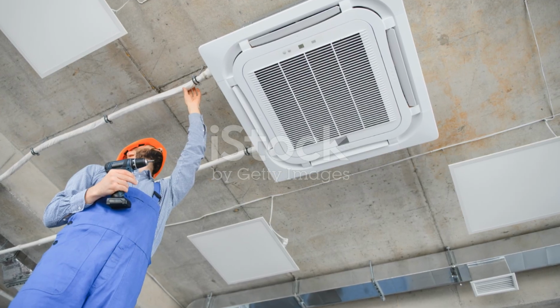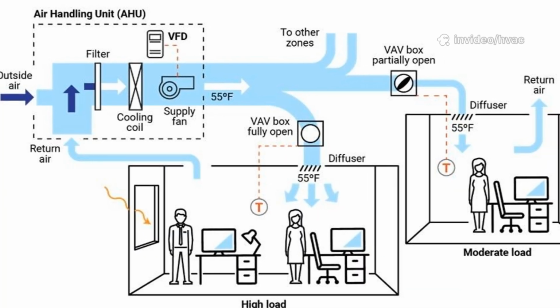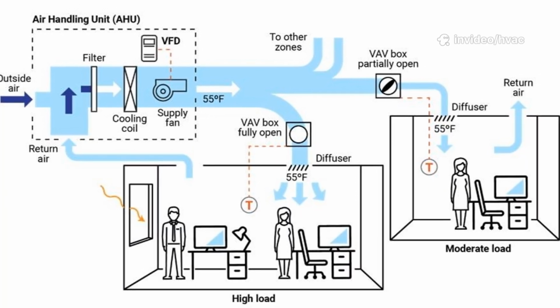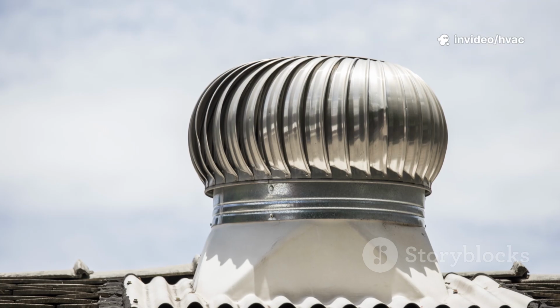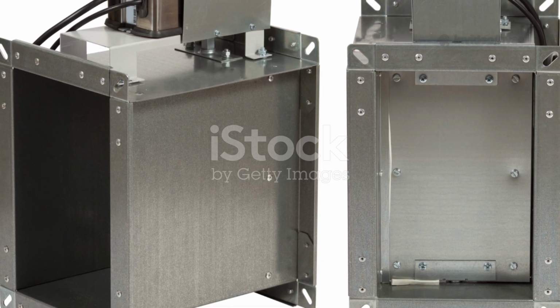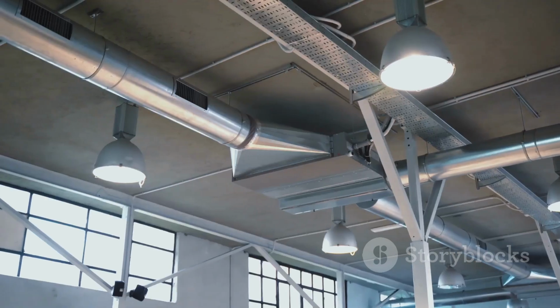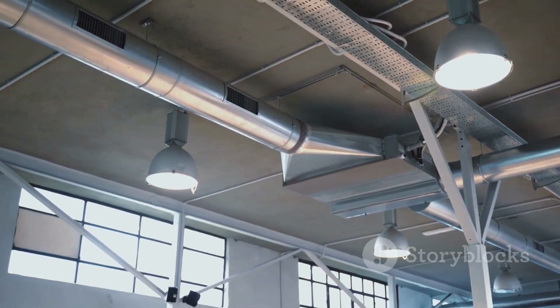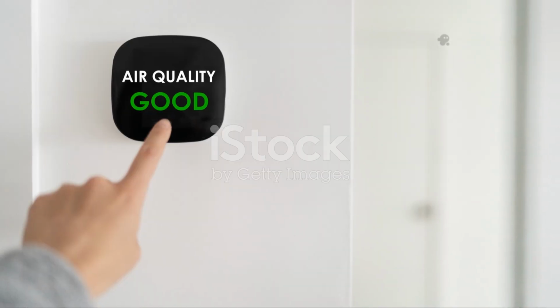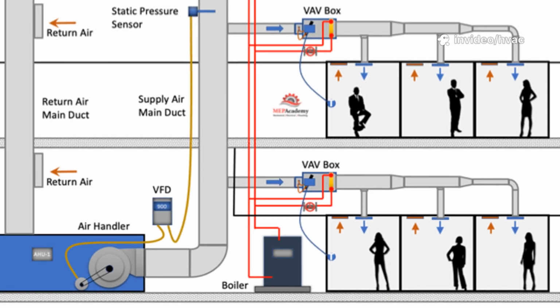No system is perfect. VAV cooling only has its considerations. First, ventilation. When dampers close, fresh air can drop below code. Solutions include programming dampers to never fully close, or using demand-controlled ventilation with CO2 sensors. This keeps air quality high but adds complexity and cost.